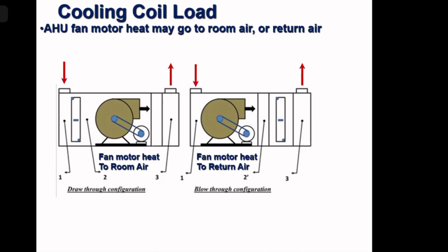So if your air handling unit is of draw-through construction, then add the fan motor heat in the room sensible heat. The other air handling unit, you see, the return air comes, it also picks up the air handling unit fan motor heat, then it passes over the cooling coil and cold air goes inside the room. So, return air itself picks up the fan motor heat before it passes over the cooling coil. So here, the fan motor heat will come in the return air part of the air conditioning system. So this is called a blow-through configuration of air handling. Here, the fan is blowing air through the cooling coil.